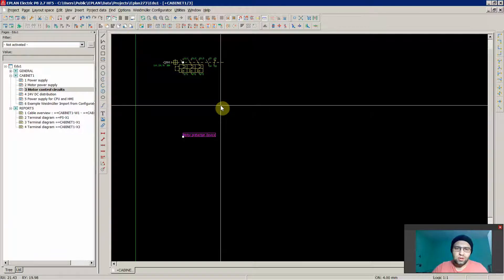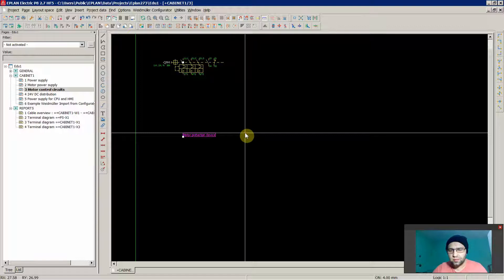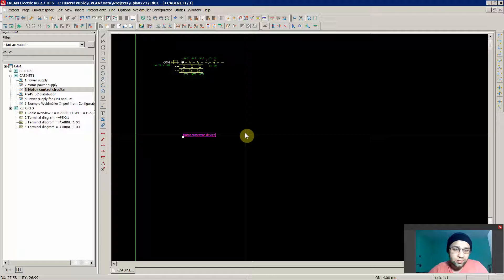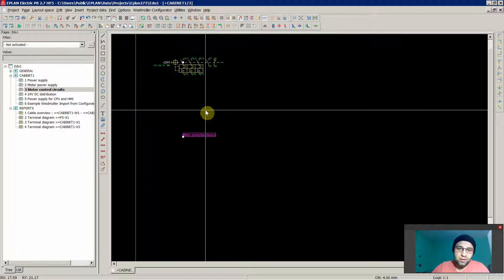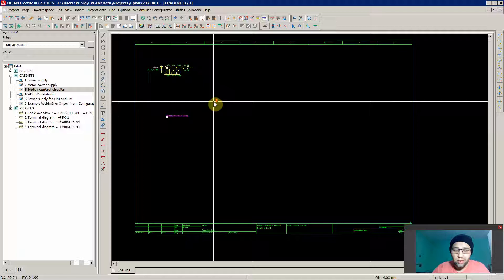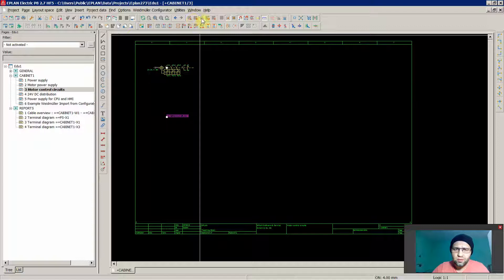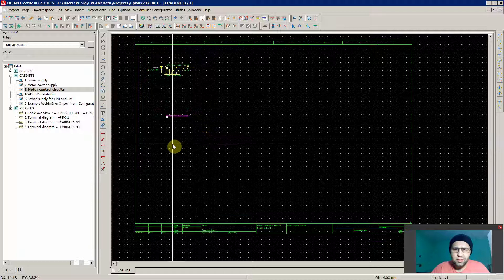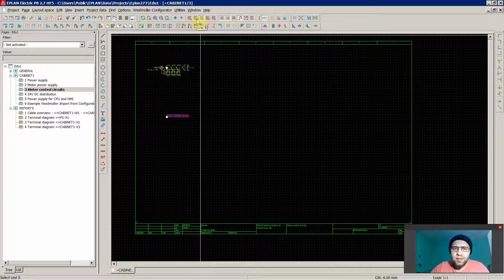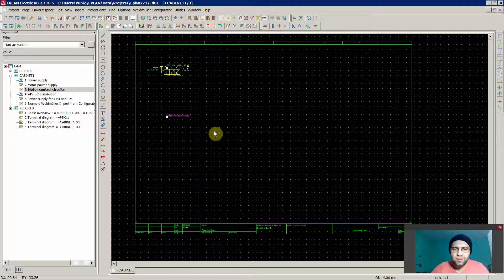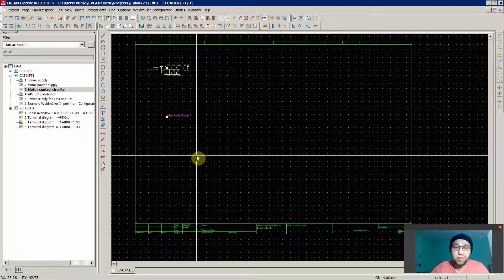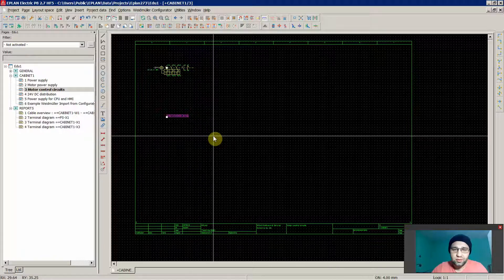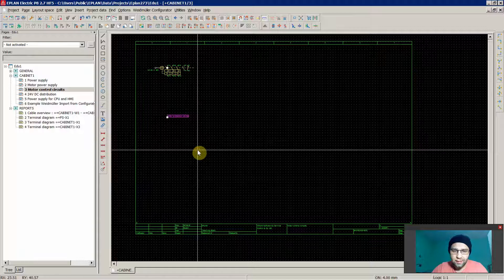You should always work and create schematics in a 4 millimeter grid according to IEC because the symbols in ePlan are also created prepared for this grid. Just as an example, as an exception, if you do want to place a little bit more elements on your page, then you would use the grid in default settings, so 1, 2, 4, 8, and 16 millimeters. If you want to see the grid, you can do it over here. As I said, normally 4 millimeters grid and as an exception 2 millimeters. Never use 1 millimeter or 0.1, it would be a disaster and would really slow down your design work.